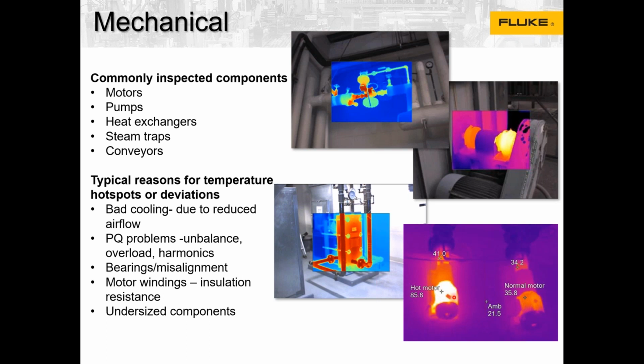It can be the winding of your motor. It can be that your motor is derating. There is something coming or a problem on your motor. It can also be vibration on your motor. So the thermal camera will give you a first indication of what's happening. Here, for example, there is an alignment problem, so you can check the misalignment with misalignment tools.